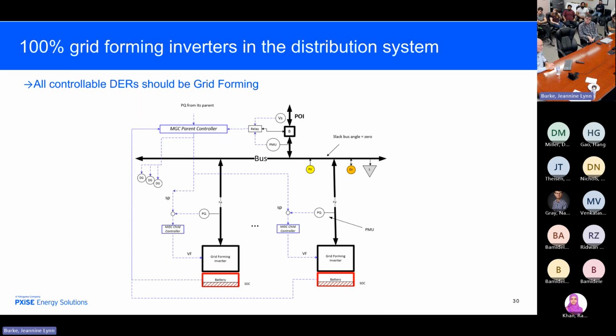Now, one last item, and that is voltage source inverters. It's a big problem in the industry. Industry is totally resistant to this. They want every microgrid in island mode, where the diesel generators form the grid. I don't care what else you say, the diesel generators always form the grid. These inverters are all grid-following inverters. We want to change that paradigm so that these are always in grid-forming mode. The diesel generators are off most of the time, and when they come on, they become grid followers. They were in isochronous mode.